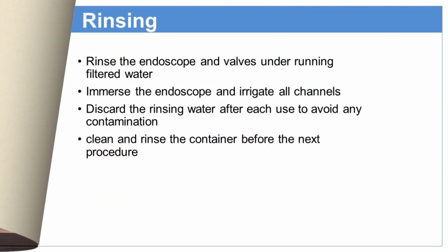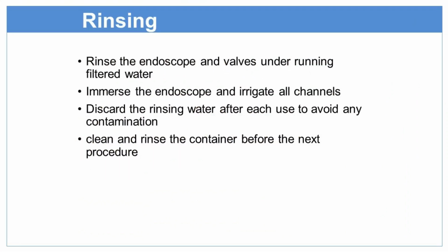Rinse the endoscope well under running filtered water. Make sure that when you have done the cleaning of the endoscope, the rinsing water is filtered or clean water. Immerse the endoscope and irrigate all channels. Discard the rinsing water after each use to avoid any contamination. Clean and rinse the container before the next procedure.